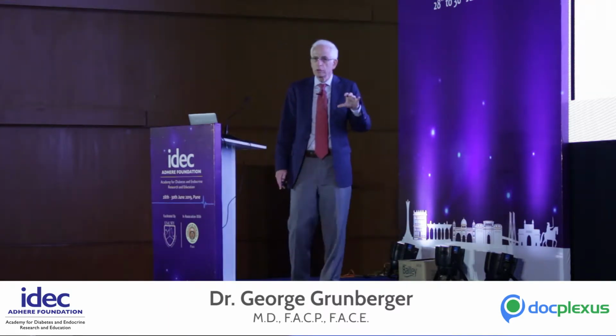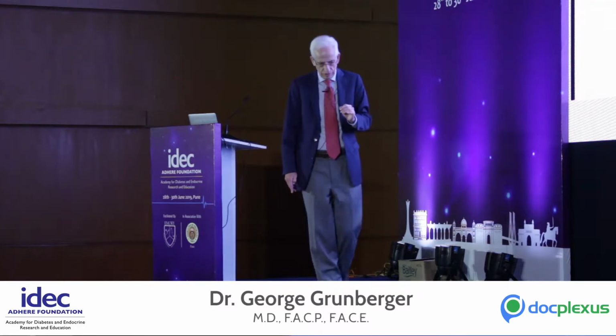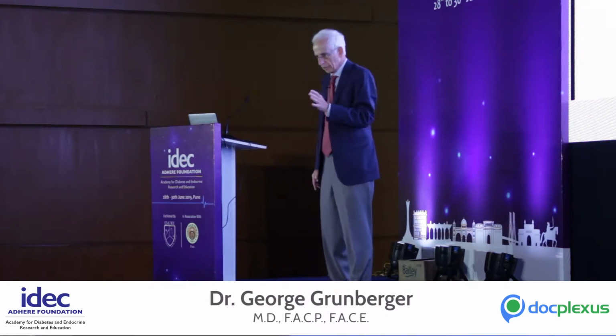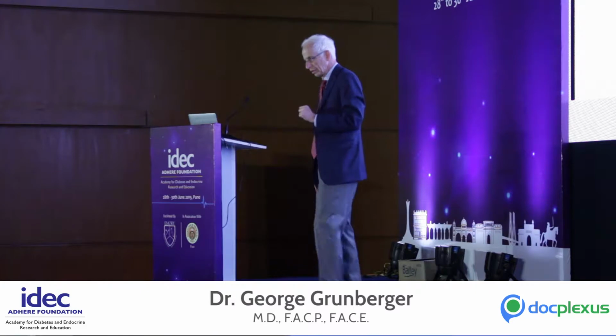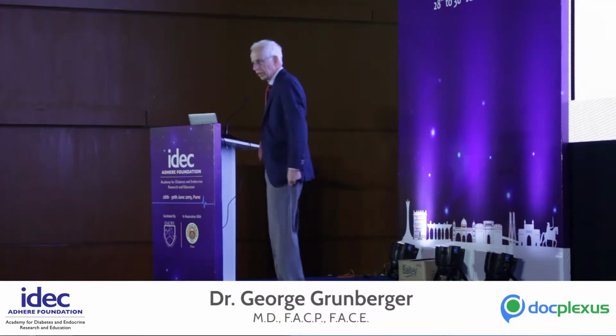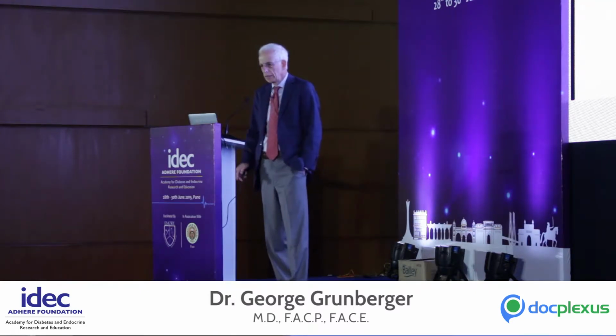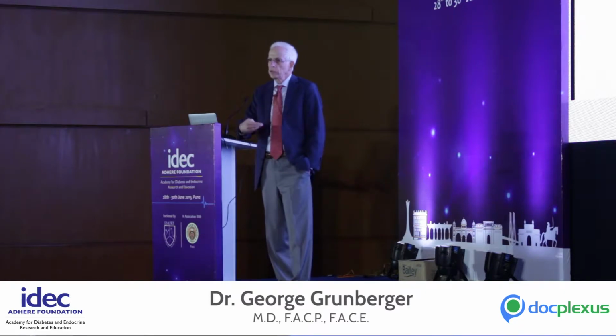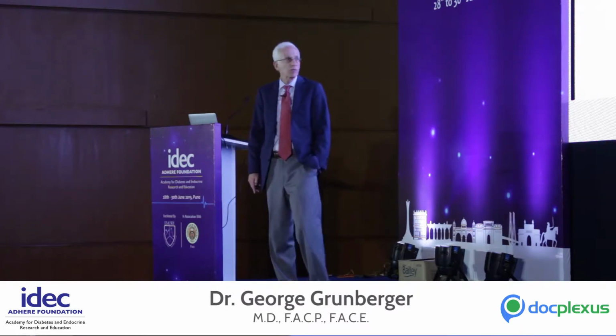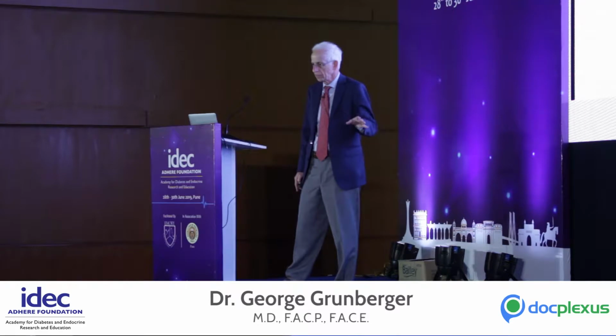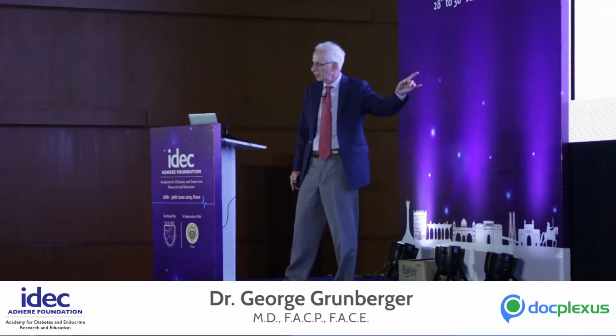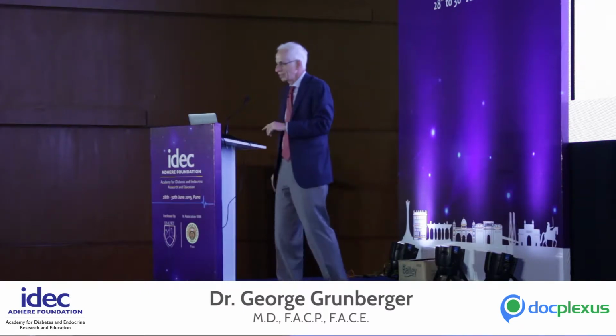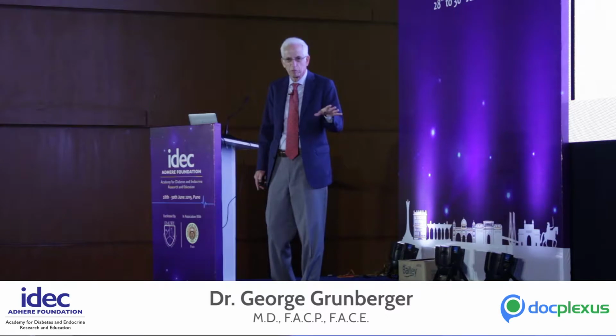There are two devices right now in the US from Medtronic, but I'll just tell you about the latest one on the market, which is the Guardian Sensor 3. That system is more accurate than the preceding systems, and it's there for 7 days. So the sensor is replaced every 7 days, and it actually has a diagnostic chip inside. If the sensor is sick, the patient gets a message: hey, fix the sensor, there's a problem.